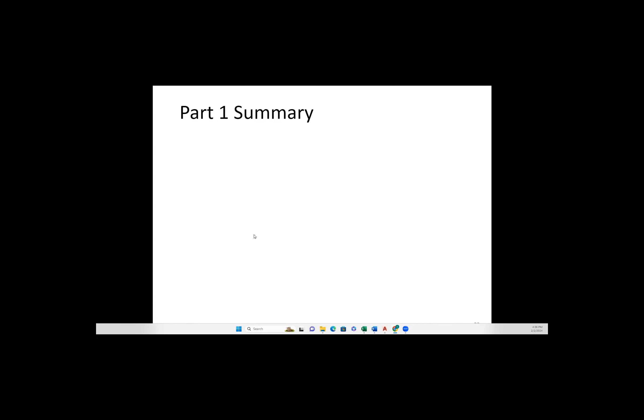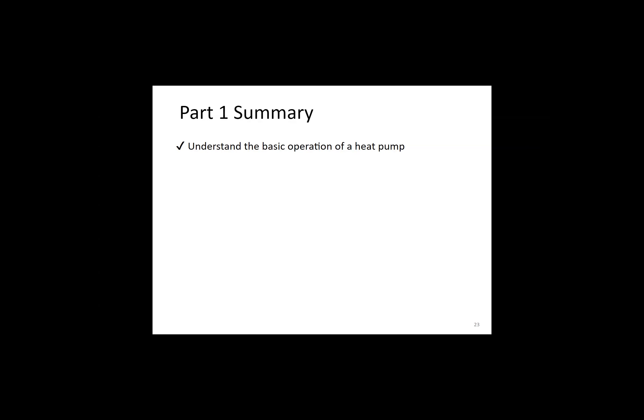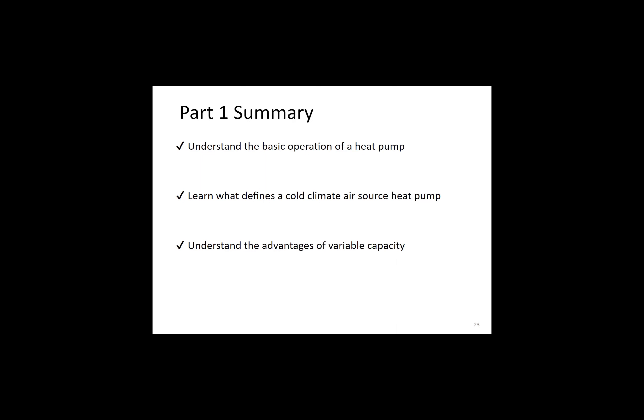To summarize part one: heat pumps move heat rather than create it — they don't burn fuel to create heat. The heat pump uses refrigerant and the vapor compression cycle to absorb heat from the outside air and transport that heat inside to maintain thermal comfort. Cold climate air source heat pumps can absorb heat from the outside air even at sub-freezing temperatures, enabled by advanced refrigerants and algorithm-driven controls. Variable capacity allows the heat pump's output to match the heating or cooling load automatically, rather than only cycling on or off to maintain temperature.